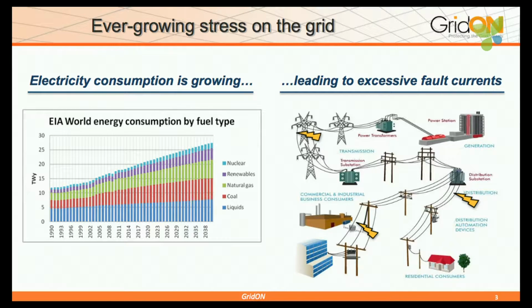With electricity consumption keeps growing, we see a lot of new energy being produced from different kinds. We heard about it. And with energy growing around the world, fault levels on the grids keep increasing. A fault is a situation when there is a short circuit on the line. If you have more power being pumped into the grid, the short circuit current level will rise.